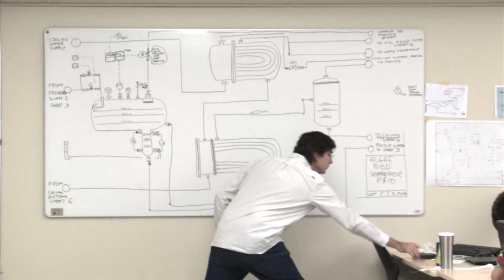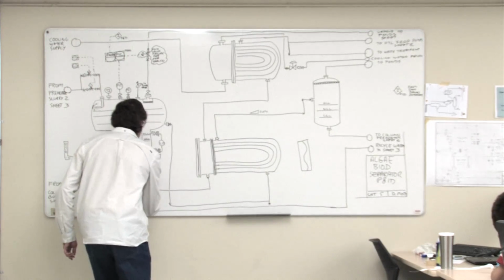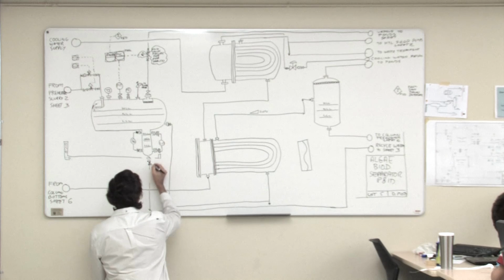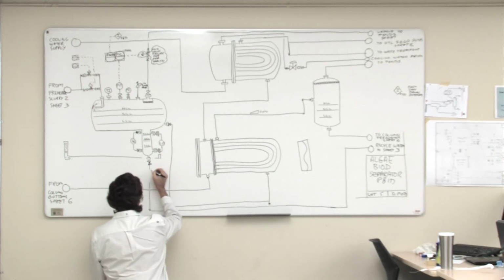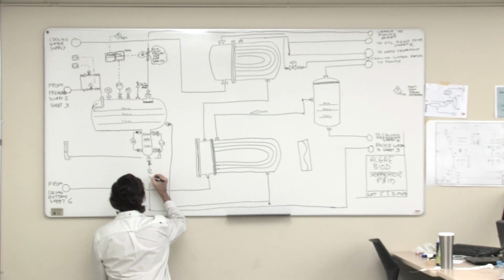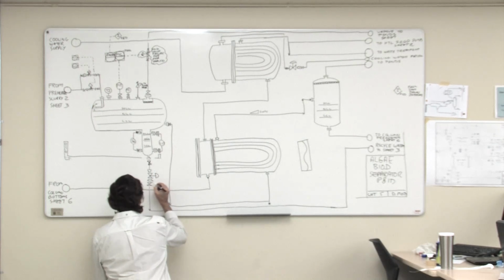And here we go. I've got a valve right there, so I'm not going to bother putting another valve. I'm just going to go down to the control valve here, down to pipe size. Put that in, go back up, pipe size, and put an isolation valve in here. That way I can pull that out.